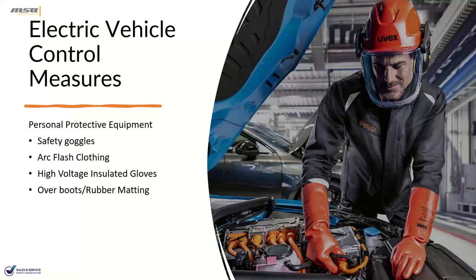The use and care of this equipment is very important. Safety goggles, face protection, and flame-resistant clothing can protect a worker from arc flash and sparks. We always want to wear full-length clothing when working on these vehicles and remove all metal items—rings, jewelry, watches, belts, pens—from the outside of the body, since in the event of a large enough arc flash, metal on the skin can melt into it.